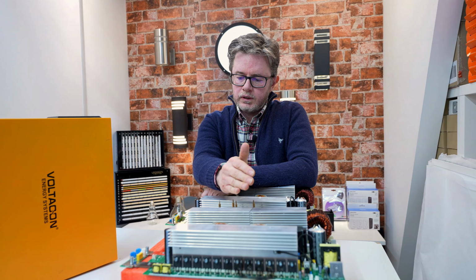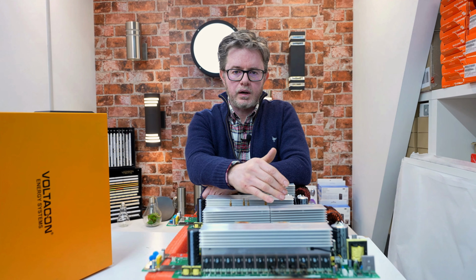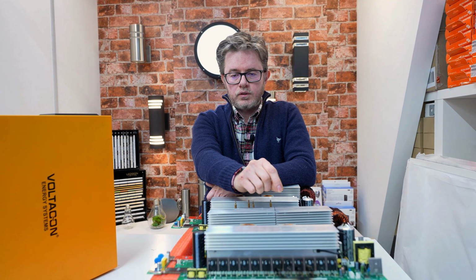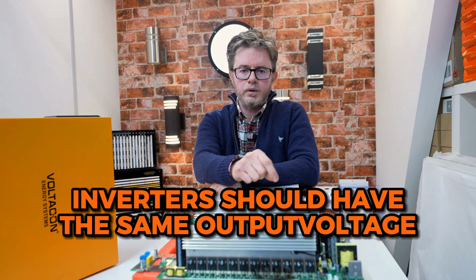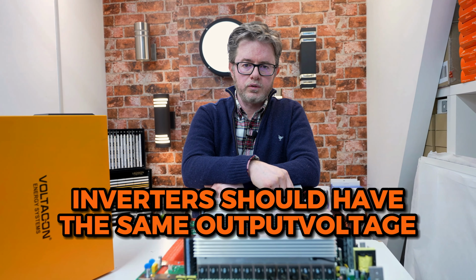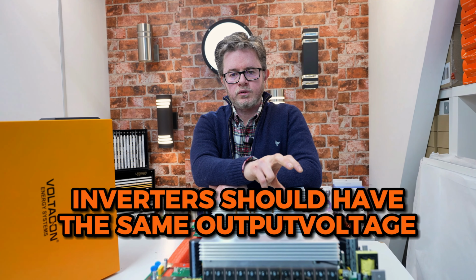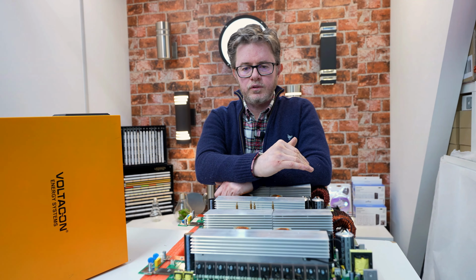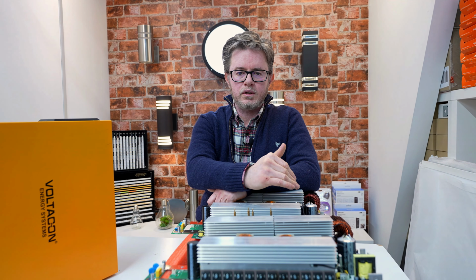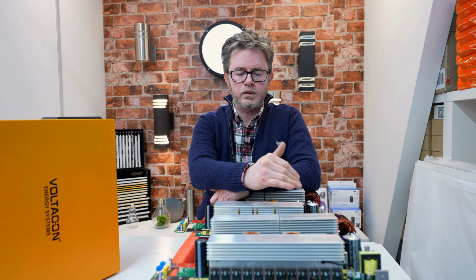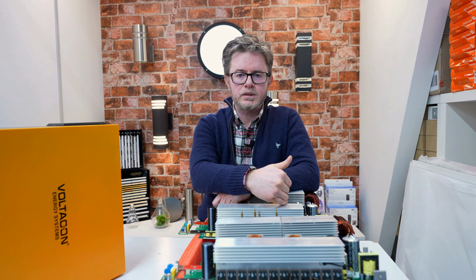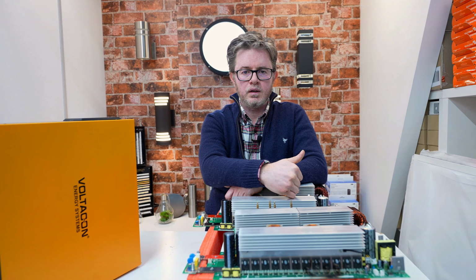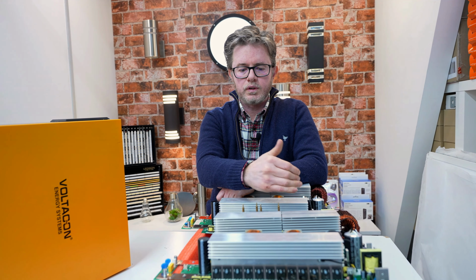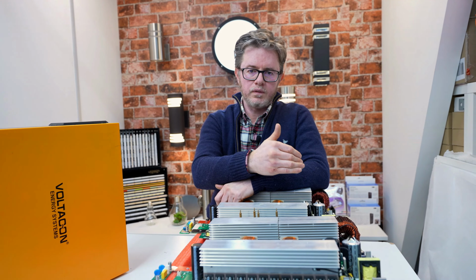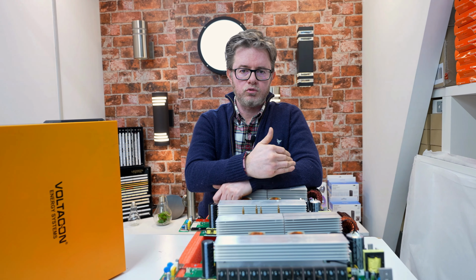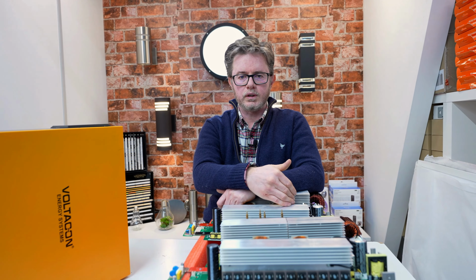The other reason is, again, when two inverters are running in parallel, one of the inverters is set to 230 volts, and the other inverter is set to 240 volts. So there is a wrong voltage, and they cannot synchronize. A different phase and a different voltage can also create a huge circulating current. When we put two inverters together, they must have exactly the same voltage without any difference, not even 1 or 2 volts. They always have to match. If it is 230, the second inverter, even the sixth inverter, should have 230 volts, or 240.